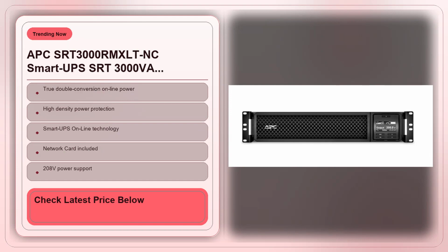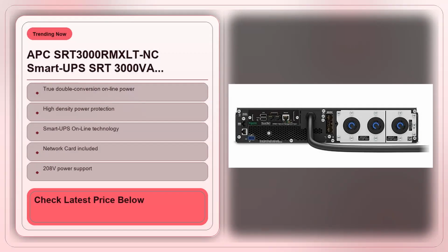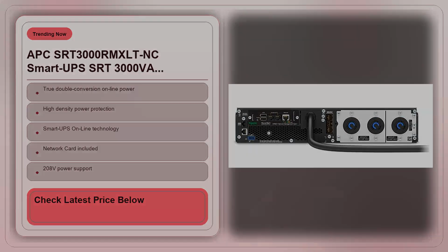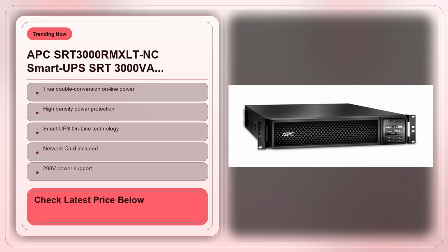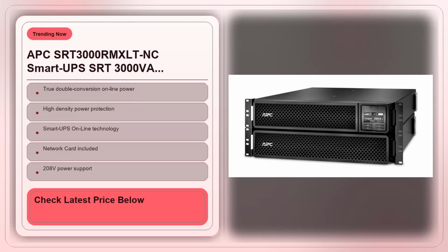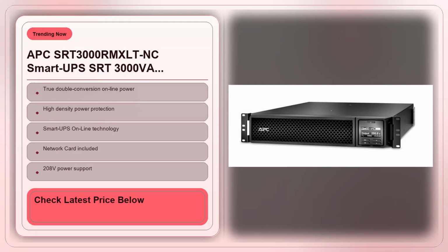The online conversion ensures zero transfer time. The moment the grid fails, the UPS is already delivering power, so there's literally no interruption to the devices downstream. In environments where you have storage arrays performing write-intensive operations, that zero-delay switch can prevent corrupt files and reduce the risk of RAID rebuilds. Another real-world advantage is the unit's scalable runtime.